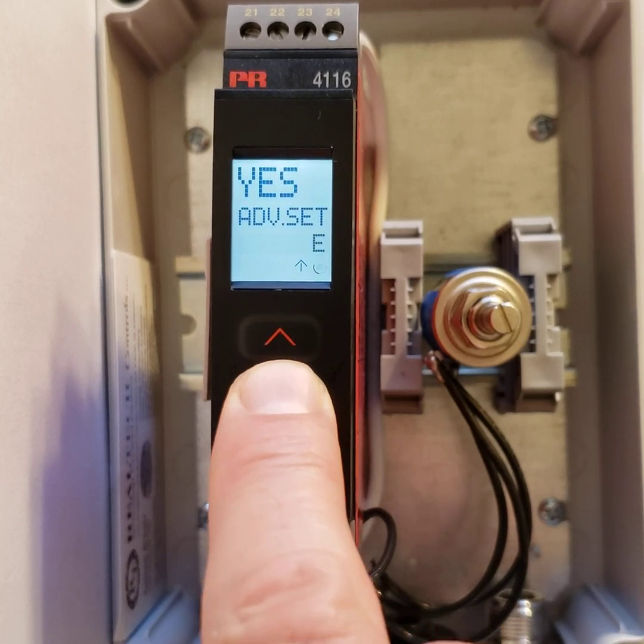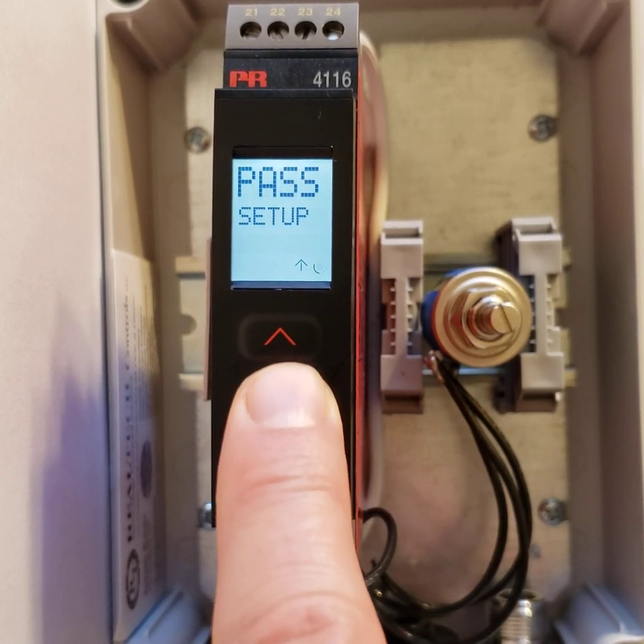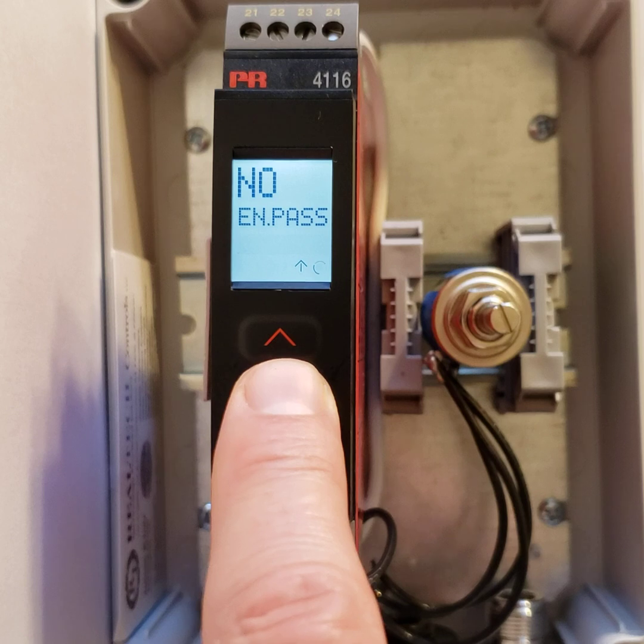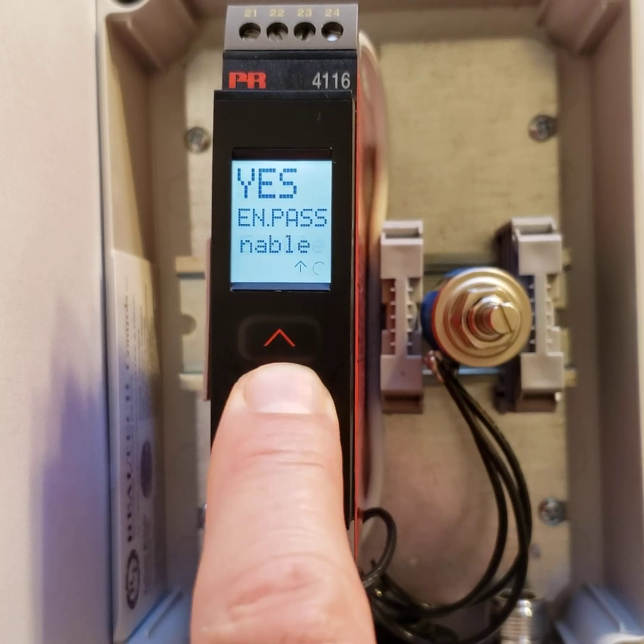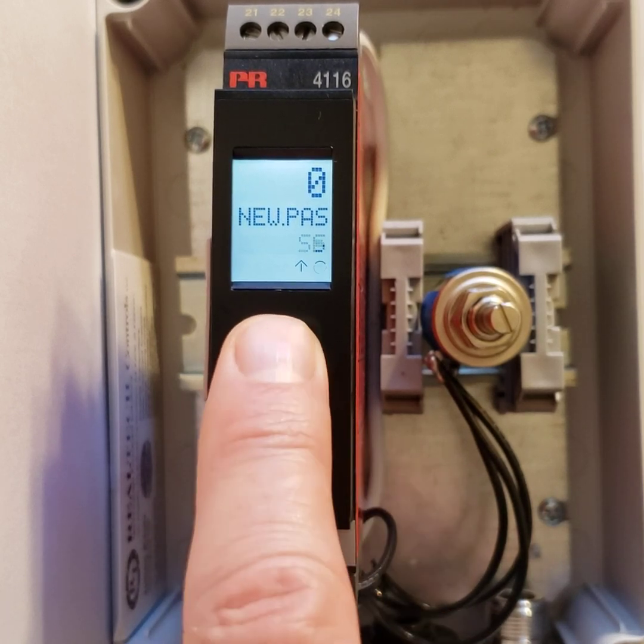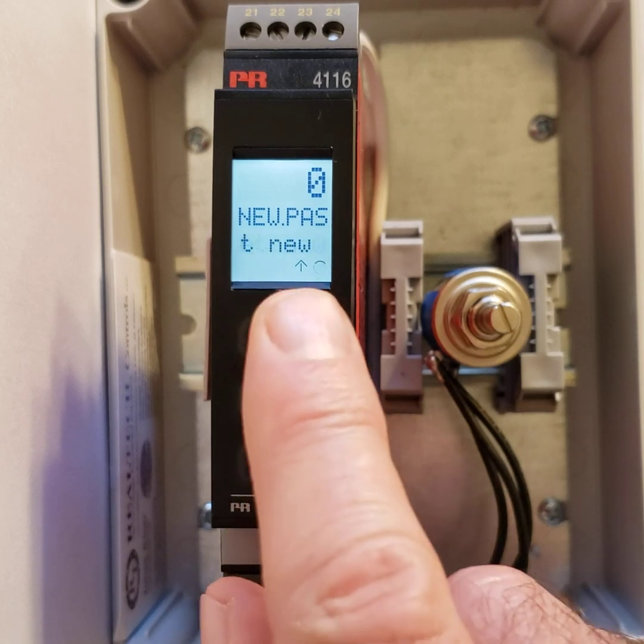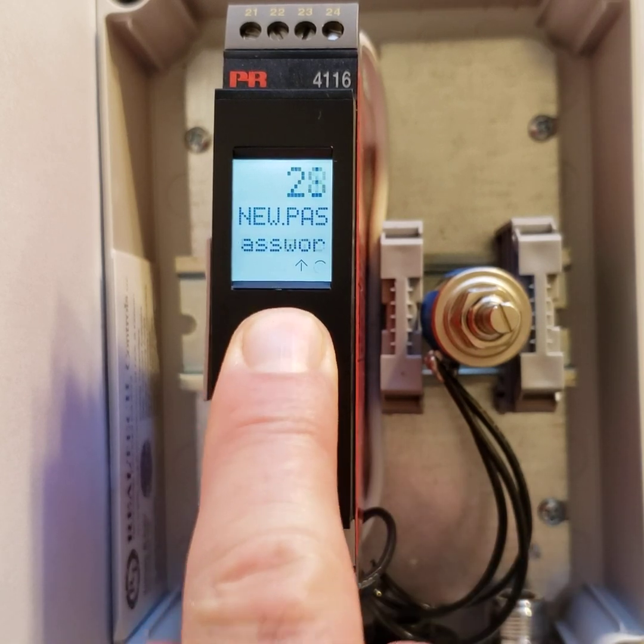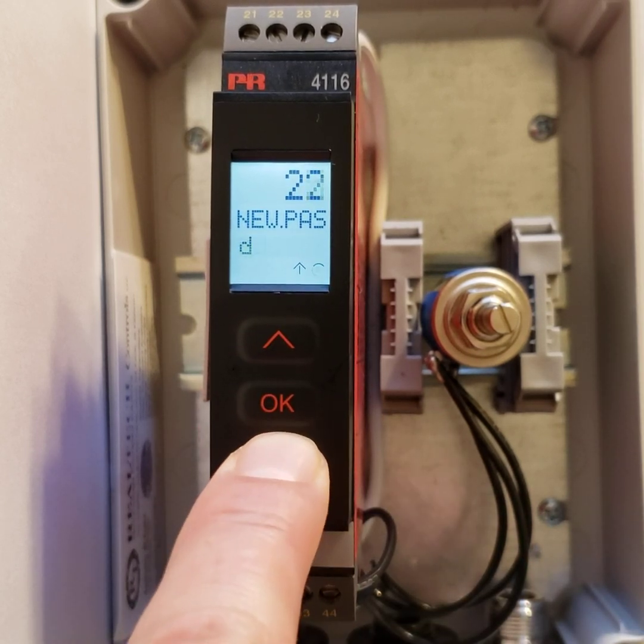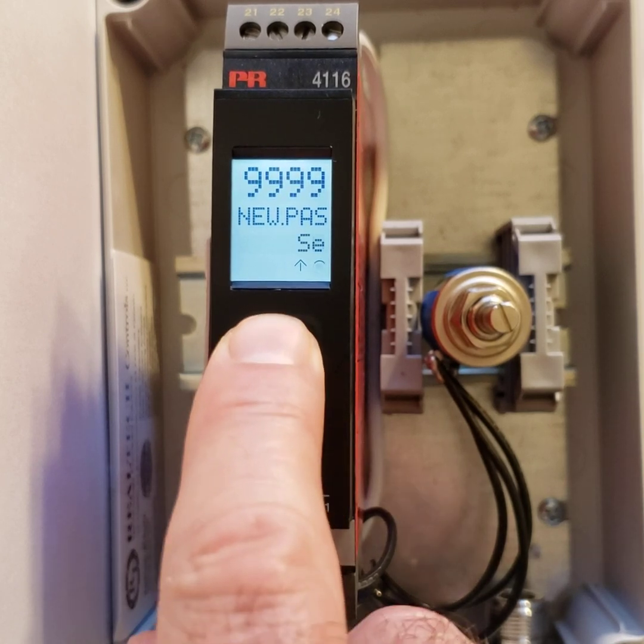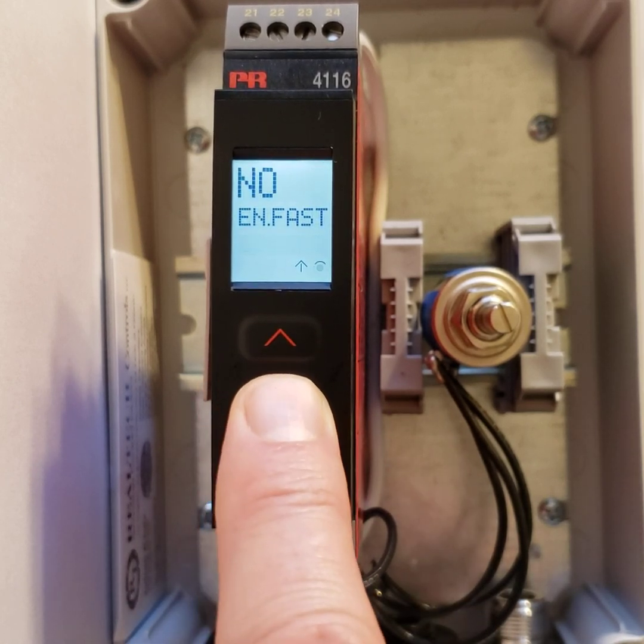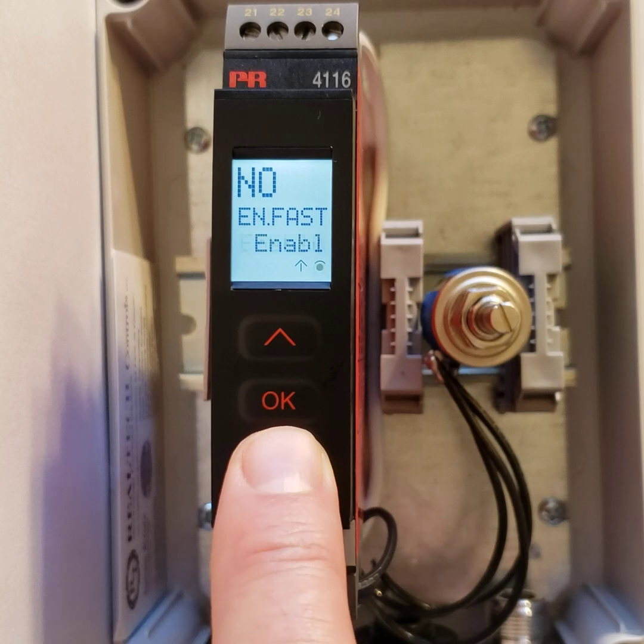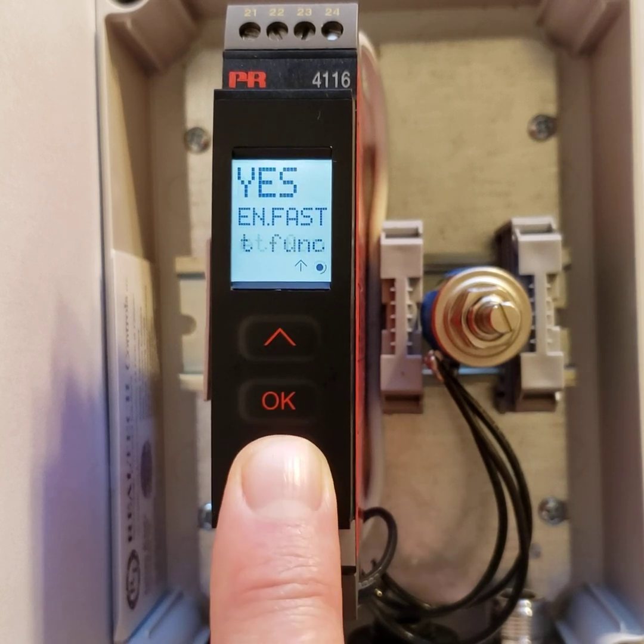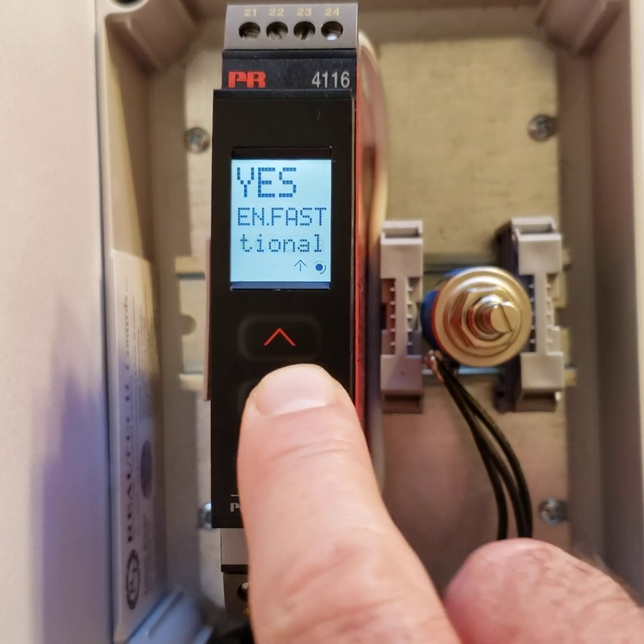The next item in the advanced menu is password. You can set up a password. If you go yes, you can set up a number that you'll have to type in once you try and access the menu again. We're not going to do that for now because we want to make this presentation a little bit quicker. We enable fast. What this does is enables you to change the set points for your relays on the actual menu itself on the home screen.